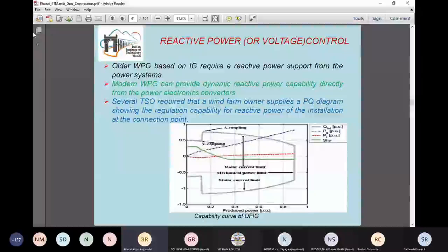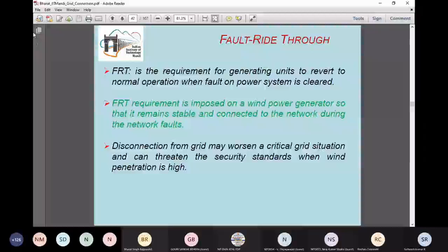So the next grid connection requirement is known as fault ride through capability. Fault ride through capability is the requirement for generating systems to revert to normal operation whenever a fault in the power system happens and is getting cleared. In this case, disconnection of the renewable energy sources from the grid is not expected. It was followed earlier, but nowadays it is expected that the wind or solar farm should remain connected to the grid and be able to inject active and reactive power. Next slide, please. One more slide, please.